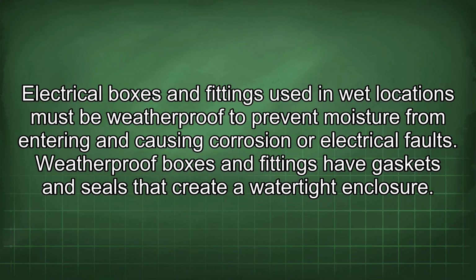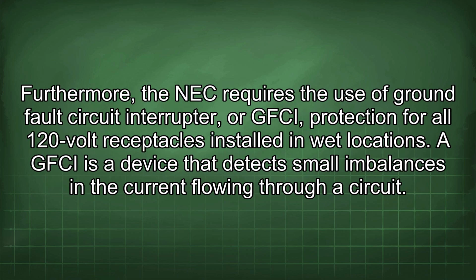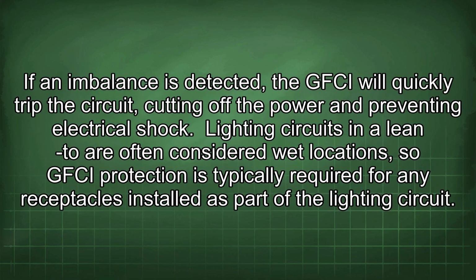Electrical boxes and fittings used in wet locations must be weatherproof to prevent moisture from entering and causing corrosion or electrical faults. Weatherproof boxes and fittings have gaskets and seals that create a watertight enclosure. Furthermore, the NEC requires the use of ground fault circuit interrupter, or GFCI, protection for all 120-volt receptacles installed in wet locations. A GFCI is a device that detects small imbalances in the current flowing through a circuit. If an imbalance is detected, the GFCI will quickly trip the circuit, cutting off the power and preventing electrical shock.